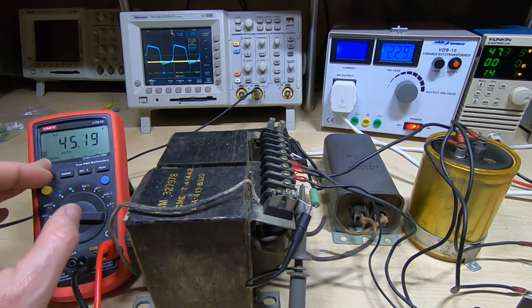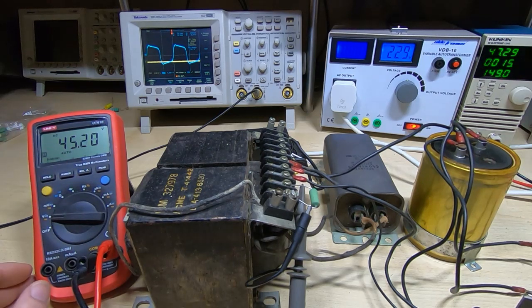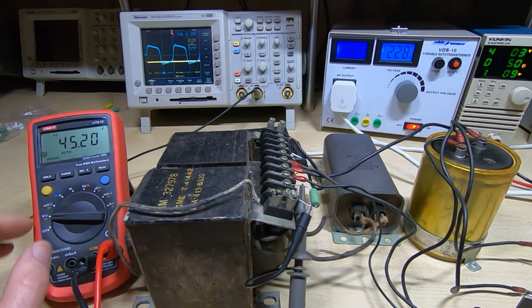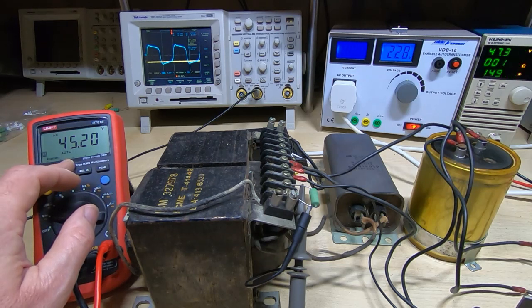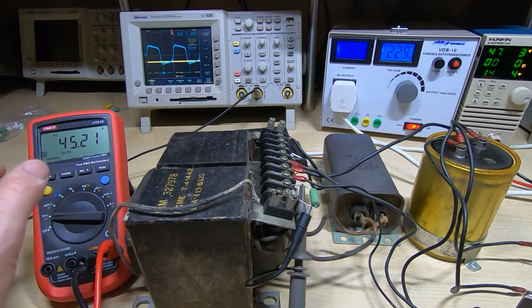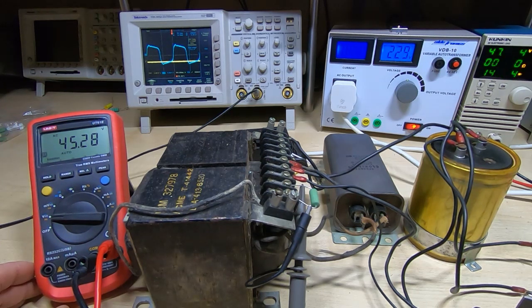produce. And so if we increase the load, for example, all we're really doing is pulling down what would have been the peak value, but we're not of course reaching the peak value because the core saturation is limiting that. And if the load reduces, then the reverse happens. We just run into saturation earlier in the current cycle of the primary.